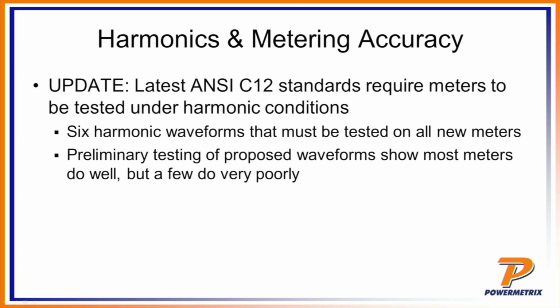Harmonic and metering accuracy: there is a problem right now in that we do not actually have a standard for VA or VAR hour metering. The ANSI C12 committee has been working on that for several years. There's one particular committee dedicated to that, and they are getting much closer to coming up with a standard way of doing it.